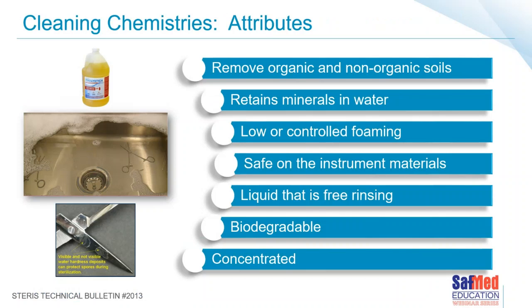So what are the attributes? What do we need from a cleaning chemistry for medical devices? We need to be able to remove organic and non-organic soils, because that's what our devices are exposed to. The non- or inorganic things can include antibiotics sometimes used in operating fields, creams and lotions applied, and cleaning solutions. All sorts of things can be deposited on our instruments — both organic and inorganic.